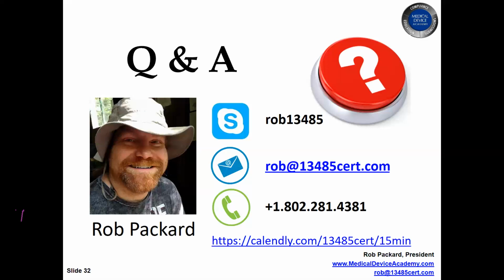The design inputs are going to be things you verify. They would be typically bench testing for the most part. There are some things that might be animal tests. There are some things that might require human testing, but for the 90%+ of them, it's going to be bench testing that you're going to be doing for design input verification. If you want to ask more questions about that, I think that's probably outside the scope of this call. And it's a favorite debate of people taking my design controls course.